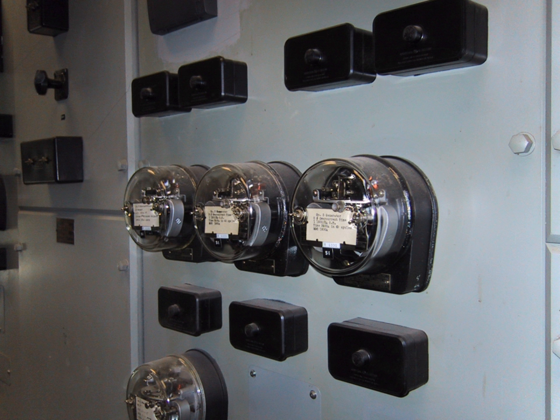Usually seven equally spaced tappings or operating bands determine the relay's sensitivity. The primary winding is located on the upper electromagnet. The secondary winding has connections on the upper electromagnet that are energized from the primary winding and connected to the lower electromagnet. Once the upper and lower electromagnets are energized, they produce eddy currents that are induced onto the metal disc and flow through the flux paths.